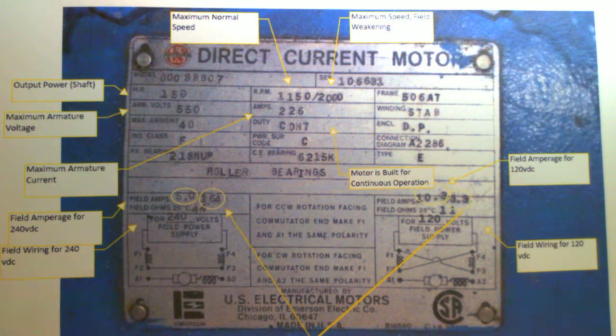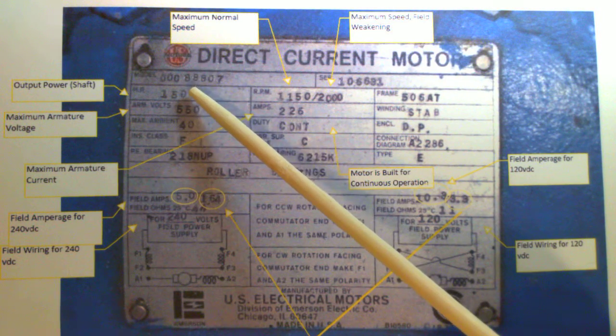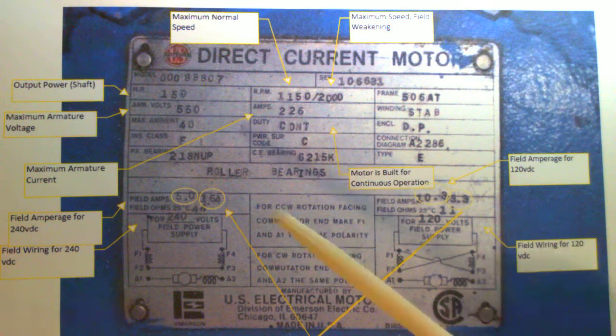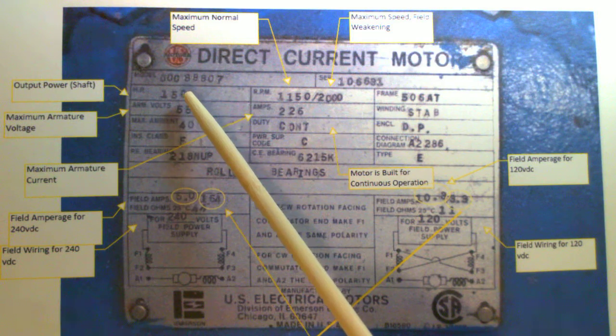Usually the first thing we look at when we look at the nameplate for a motor is this thing right here. Horsepower. What you need to commit to memory is when you see horsepower on a motor nameplate, that is the output horsepower or the horsepower that the shaft can put out. I do believe that sometimes it's called brake horsepower. So in the case of our motor, this motor is capable of delivering 150 horsepower to its mechanical load.